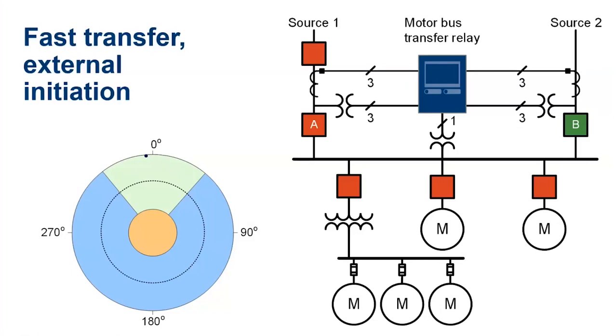And so in this case, if we get an external initiation, it's like a signal that we need to transfer. So the first thing that would happen is we will send an open command to the breaker connecting the bus to the feeder. And in this case, we have a sequential transfer, which is common and avoids feeding the fault. So after we send the open command, the bus will shift instantaneously from the frequency of the system to the slip frequency, the average slip frequency of all the induction motors in that bus. Okay, and with that, the magnitude of the voltage is going to start to decay because we are separated from the system, and the angle is going to start to separate.